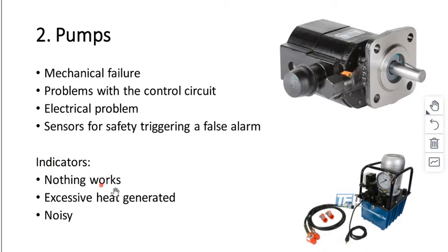So indicators that the pump has gone down: nothing works. There's excessive heat generated around the pump. So that could be an electrical fault if there's an electric motor where some windings have burned out or something. And it's noisy as well. It can be noisy. Yeah. So for example, it's just a mechanical device. So we've got bearings in here.